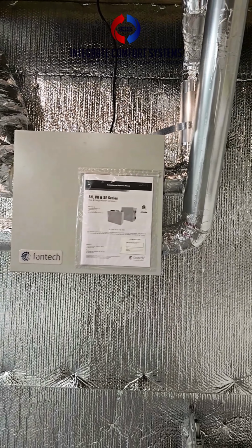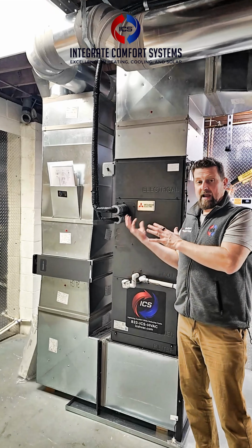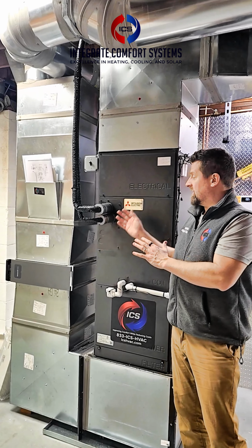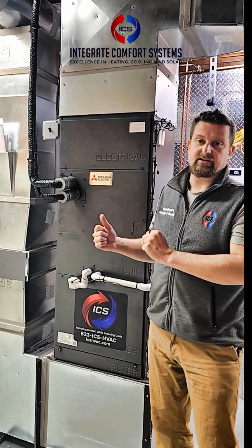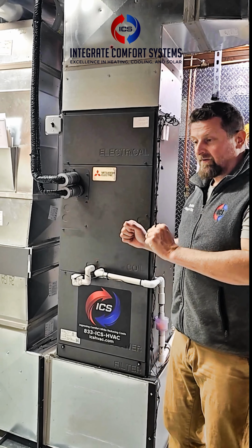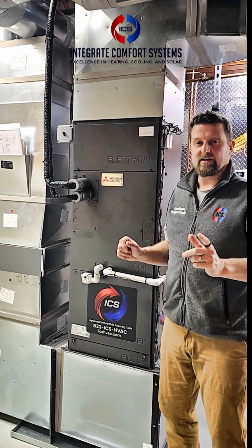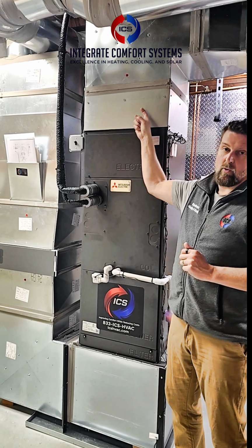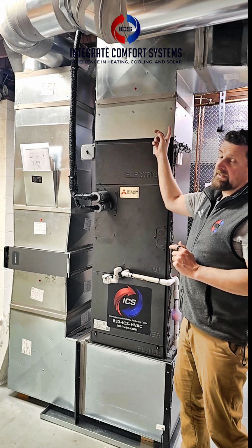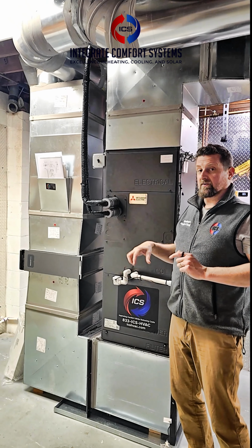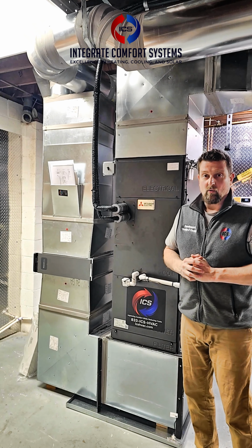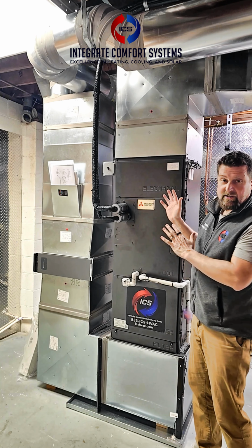Let me explain what these are. What we have here is a high-efficiency Mitsubishi Hyperheat system. It's here for comfort and efficiency, but on this project we paired it with a hot water reheat coil. So this is not a hot water coil used for heating, it's used for reheating. Let me explain what the difference is.